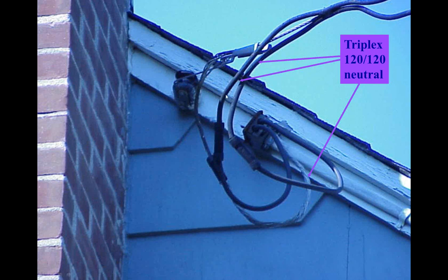So think of it like this. I've got two hot legs of 120 coming in. I can take it into the house and turn it into 240 for the dryer, for those things that need 240. But most of your house runs off one side or the other. If you ever have flickering lights, so the wind blows and it's blowing around a little bit, you've got flickering lights, you have a problem with either a neutral or one of your hot legs. You call your utility immediately and tell them you have flickering lights, and get somebody out there to check that out immediately.